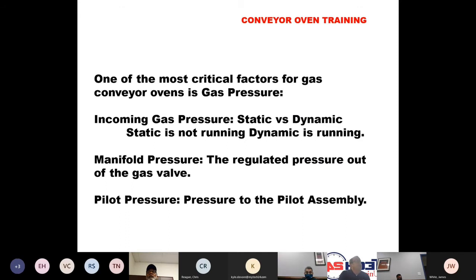One of the most critical factors for gas conveyor ovens is gas pressure. And I really can't emphasize this enough. I've seen so many problems over the years on pizza ovens that came back to gas pressure or gas volume that had not been checked. So we typically are going to look at 3 pressures. The first pressure we're going to look at is incoming pressure. And we're going to look at static pressure versus dynamic pressure.